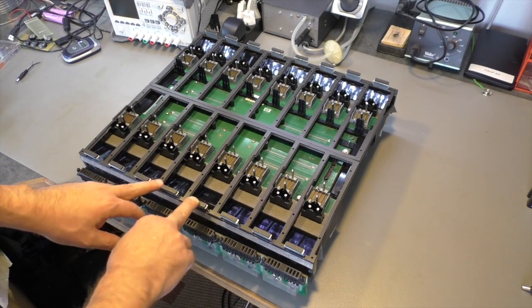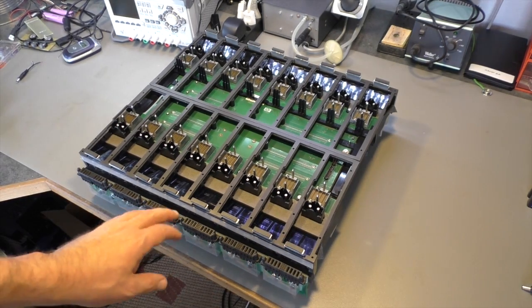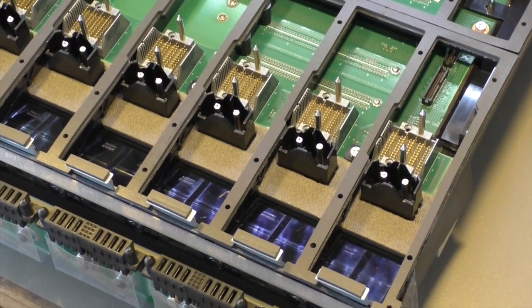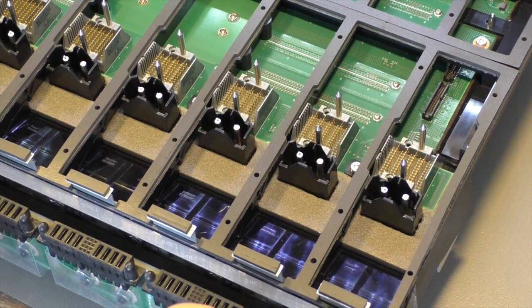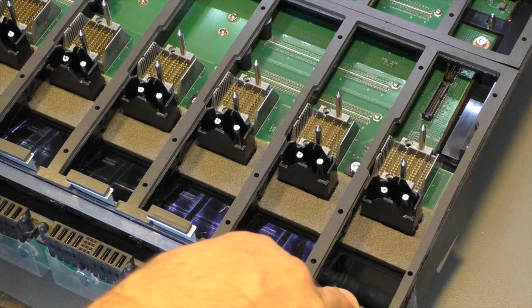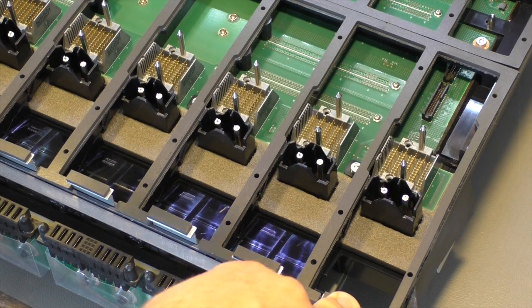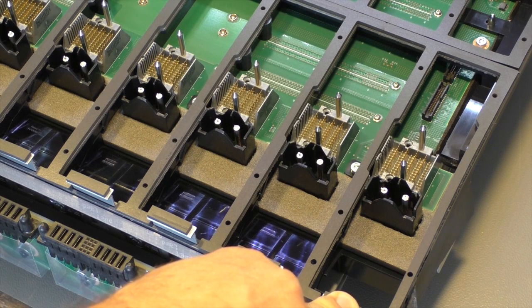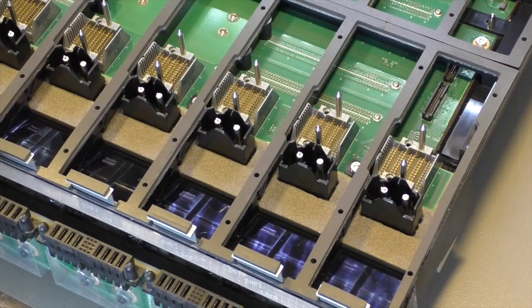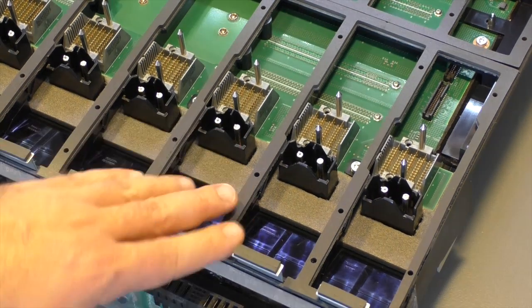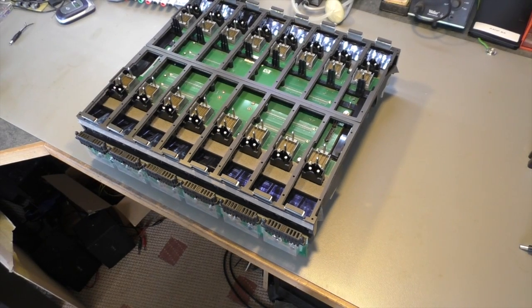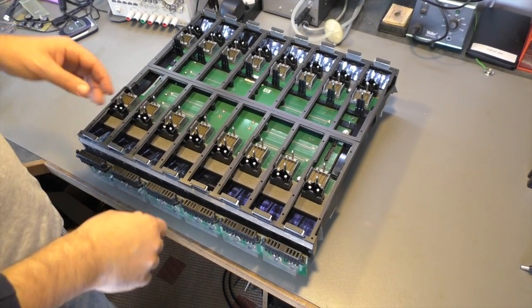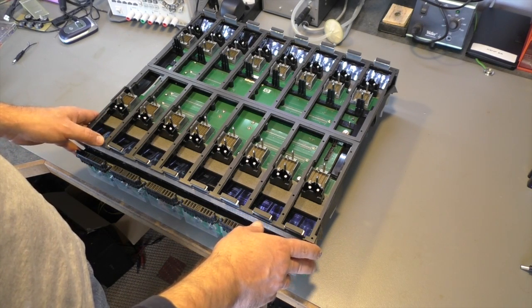These little doors here - they look like small garage doors. They open when you install a server into this bay. You slide the server in, the garage door opens, and the airflow goes through that opening. If you have no server installed, the door is closed and the airflow goes to the other servers. So each slot has its own opening for the airflow.